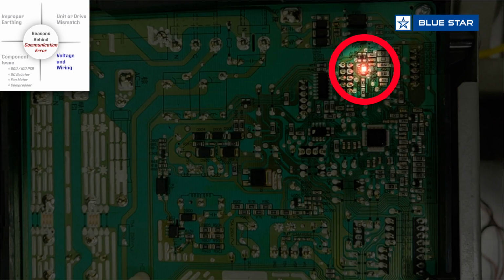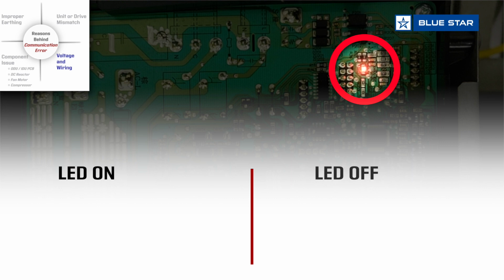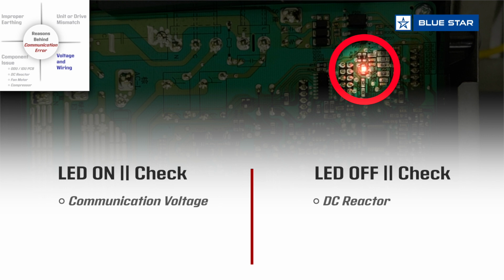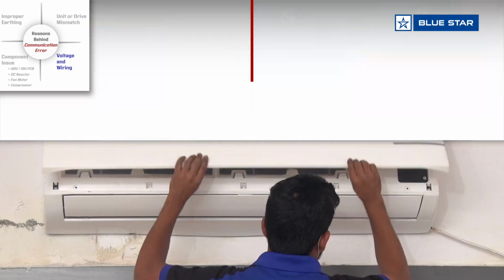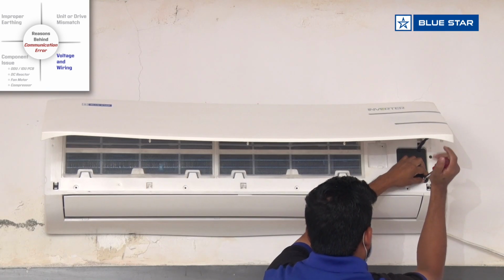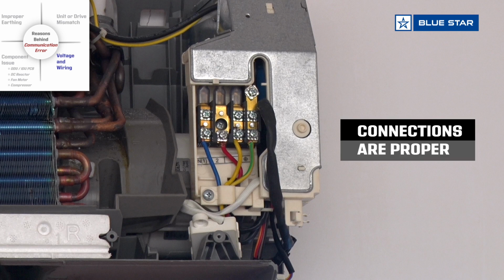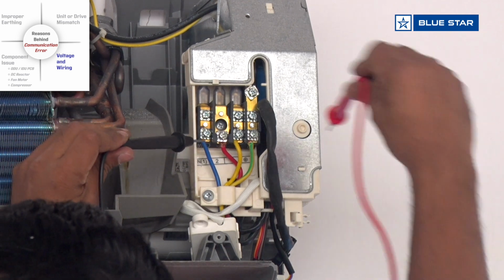Errors are further classified based on the LED at the ODU drive being on or off. If the LED is on, then we need to check communication voltage. And if the LED is off, then check the DC reactor, fan motor, and compressor. In this scenario, the LED is on, so we need to check communication voltage. Open the IDU cover and first check for any loose connections.